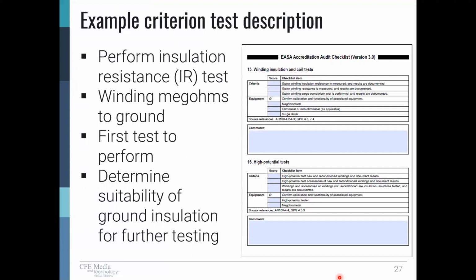If the winding to ground insulation is not good, then there's no point in doing other tests like a high potential or over potential test to ground or a surge test and so forth. It's already telling us that the machine is not suitable for repair. If we do get a good result, then it says move on and do some other tests. So we're determining the suitability of the ground insulation for further testing.